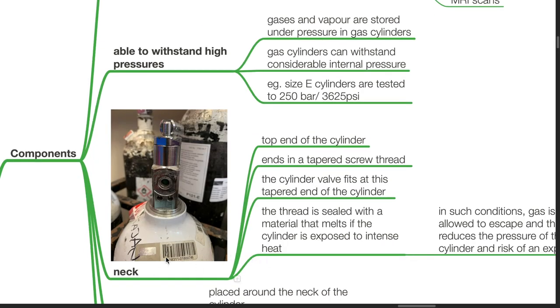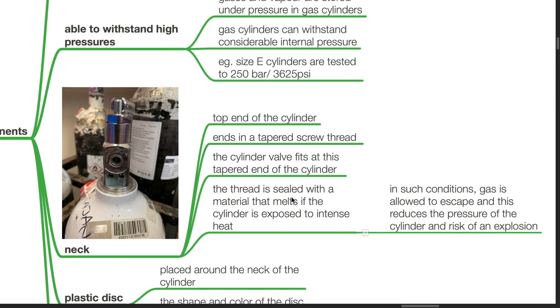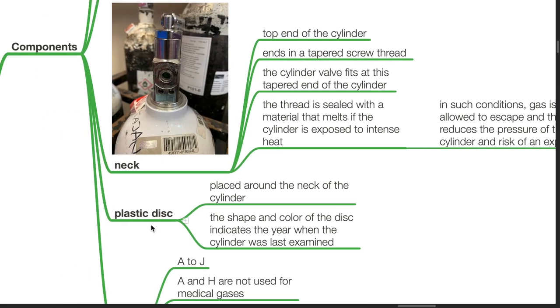The neck of a gas cylinder is the top end of the cylinder. It ends in a tapered screw thread. The cylinder valve fits at this tapered end of the cylinder. The thread is sealed with a material that melts if the cylinder is exposed to intense heat. In such situations, gas is allowed to escape and this reduces the pressure of the cylinder and reduces the risk of an explosion. A plastic disc is placed around the neck of the cylinder. The shape and colour of the disc indicates the year when the cylinder was last examined.